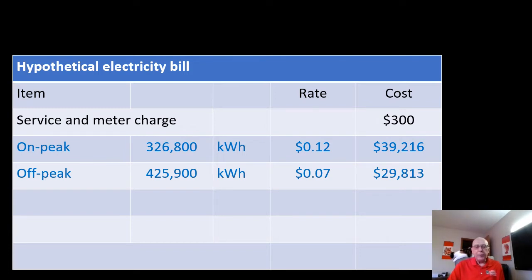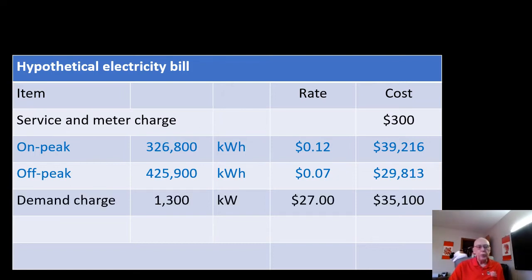There is, generally speaking, also another component in your electricity bill that tends to be large, and that is often referred to as the demand charge, although different utility companies may have different terms for this. This demand charge is based on your power use during the 15-minute period, during each billing cycle, during which you use the most power. And in the case of a greenhouse with supplemental lighting, that would typically be a period that you have all of your supplemental lights on.